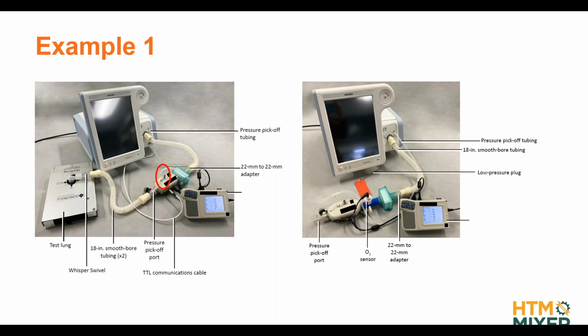the complexity of this setup is based on that specific model of gas flow analyzer. It has a lot of different modules. There's a user interface, a measurement module, then you have the T-in pressure, then you have a cable here, you have a trigger cable. Over here, you also have where you need to measure oxygen, then you need to tee in an oxygen analyzer. I'm not saying that this is a bad analyzer, this is a very good analyzer actually, and one that is very often used in the field. But the whole complexity of this setup is just based on this one analyzer they are showing you. So what if you want to use a different analyzer? Then you need to figure it out yourself, right? There's absolutely no help from the manufacturer on how to set up your measurement setup.